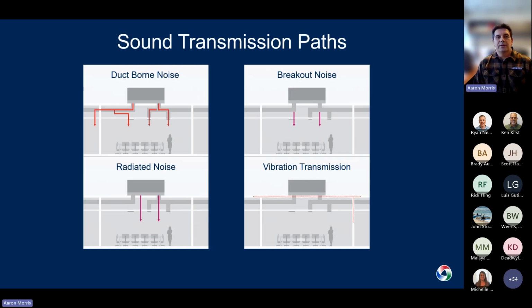Now we can get started looking at what you need to consider when looking at a design. You're going to have a piece of equipment that's going to be your source of noise, and then depending where that piece of equipment is located next to your space, you'll need to consider all four of these sound transmission paths. So you're going to have ductborne noise, where the sound is traveling through that ductwork. You're going to have the breakout noise, where the sound breaks out through that ductwork and goes down straight into the space or to the sides.